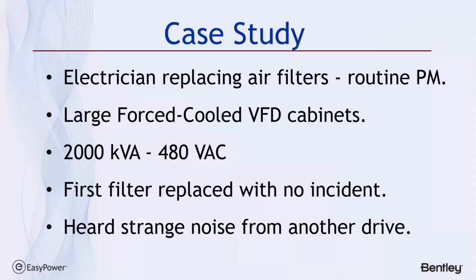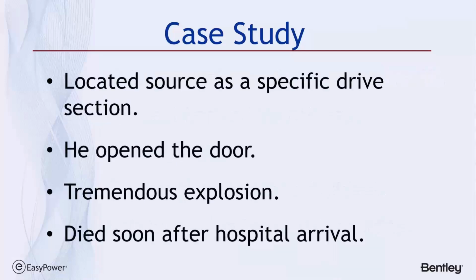I'd like to start with a case study that I found in the accident report section of the OSHA website. It involved an electrician replacing some air filters as part of a routine preventive maintenance procedure on a bank of large forced air-cooled VFD cabinets that were supplied by a 2000 kVA 480 volt substation. He had replaced the first filter without an incident, and he heard a strange noise coming from another cabinet in the utility room. So he decided to investigate. He did so by opening the door and poking his head in to see if he could locate the source of the sound. The first 2 or 3 cabinets that he opened, there wasn't a problem, but the last cabinet he opened produced a large explosion, knocked him off his feet, and unfortunately he died shortly thereafter.